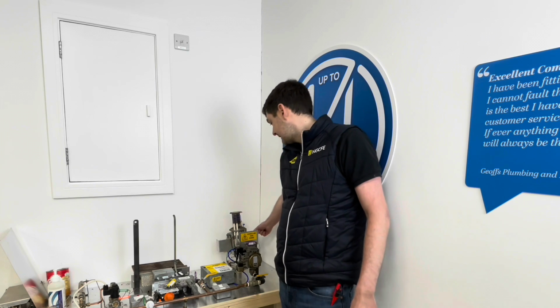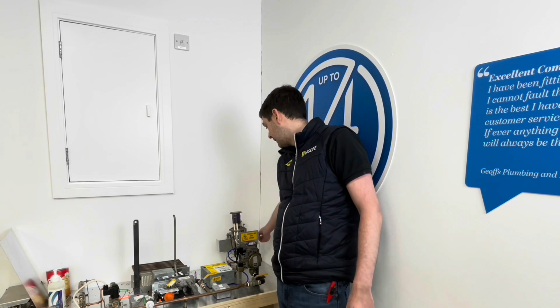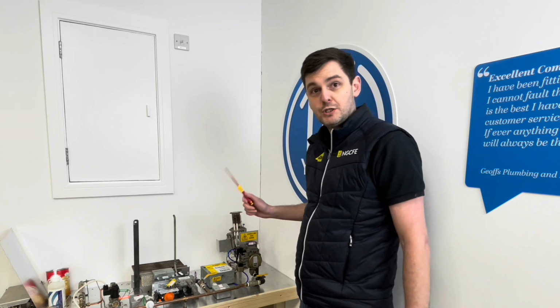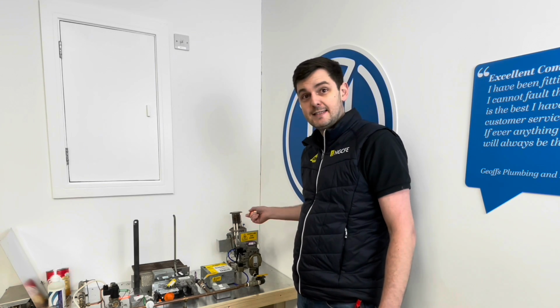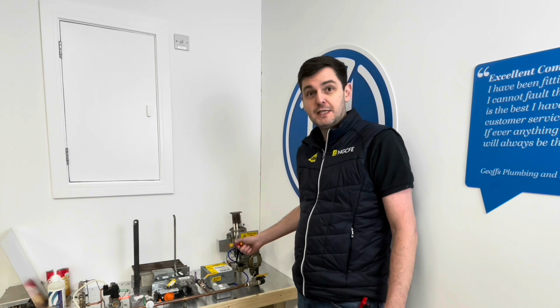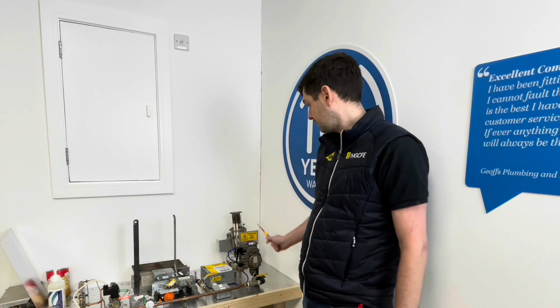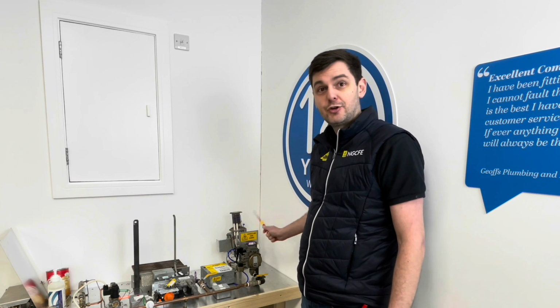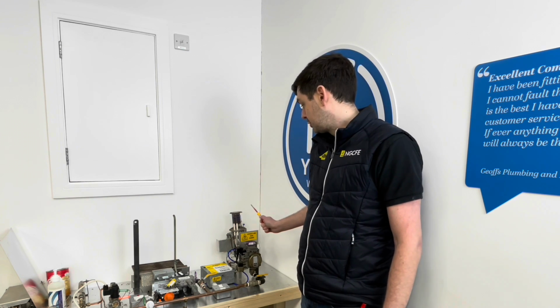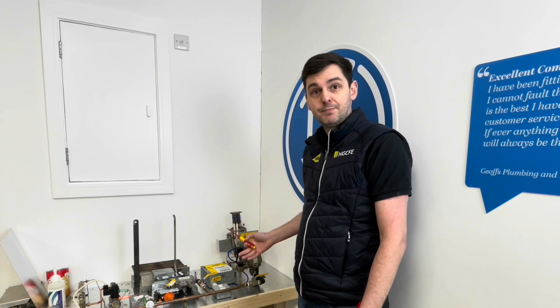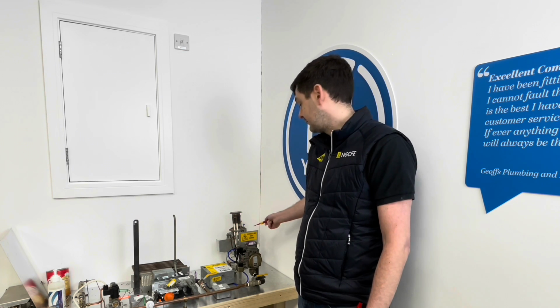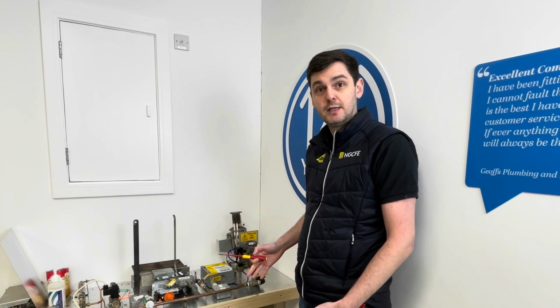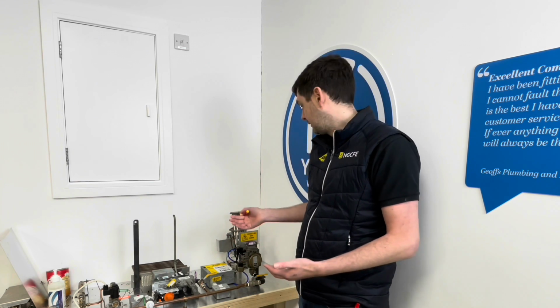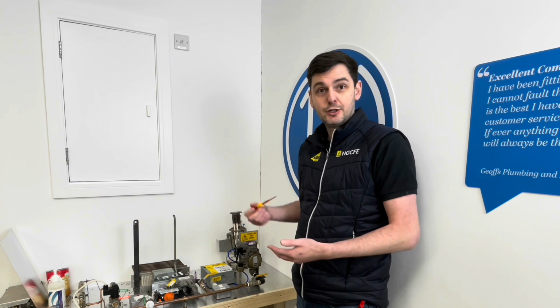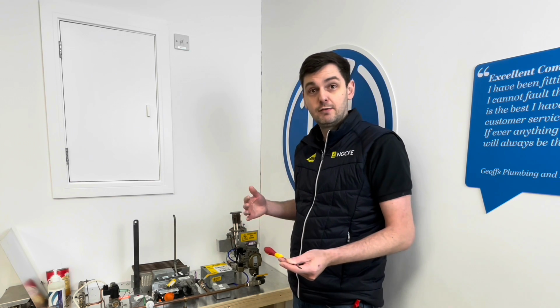If I was to disconnect the flame rectification probe and break the circuit, what we'll notice now is that the flame will light, but the board won't receive DC current and it will continue trying to ignite because it doesn't know that there's a flame present. See, it's still trying to ignite. That's because the board isn't receiving DC current back. There's no way of the AC current present at the rectification probe getting back to the board. So therefore it goes to lockout. Well, it goes to a failed ignition sequence, and it'll try that 5 times before eventually going out to lockout.